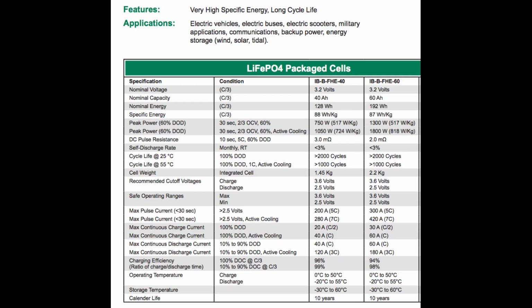The specifications for the lithium iron phosphate traction batteries give a lower limit of 0 degrees centigrade, an upper limit of 50 degrees for charging. But just to be safe, I try to avoid charging below 10 degrees, so I plan to make 10 degrees correspond to the lower limit of normal on the gauge, and I'll keep the upper limit at 50 degrees. The thermistor resistances, which I've verified experimentally, are 19,200 ohms at 10 degrees and 3,560 ohms at 50 degrees.